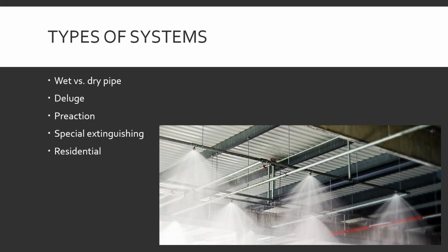where the alarm goes off, system opens, and gas fills the room, and there's no oxygen anymore, and the fire goes out, and it doesn't get water all over the electrical equipment. You might be able to salvage more from that, or if it's a false alarm and it goes off by accident, then soaking your entire server farm with water, kind of thing.